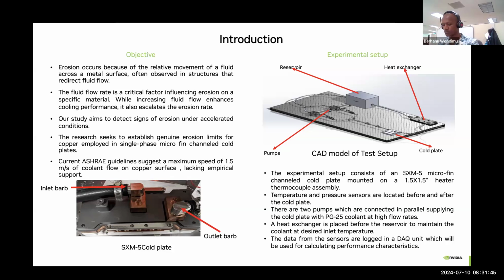In this study, we looked at which locations achieve the highest velocities. We saw that it will be at a barb, because that is an area that gets constricted, and the velocity can go much higher. It can be where the coolant enters the cold plate and hits the surface at the bottom of the cold plate. Inside the cold plate, velocities are usually very low because the coolant gets distributed into multiple fin channels, so velocities drop drastically and it is mostly a laminar region.